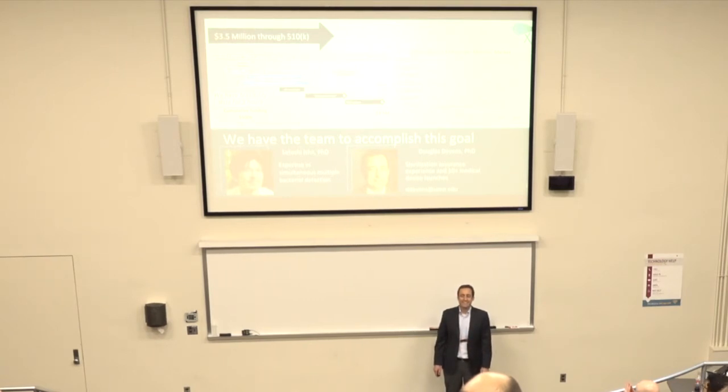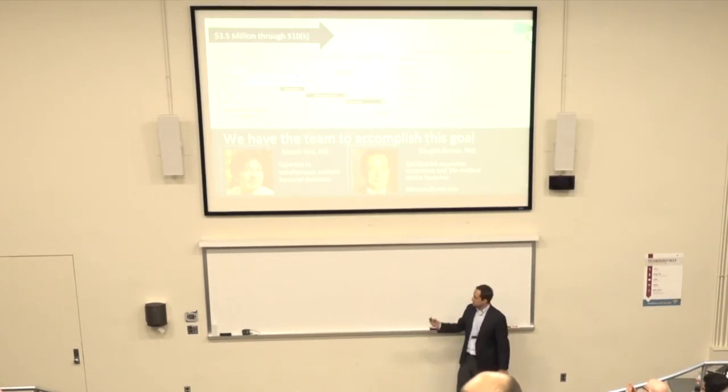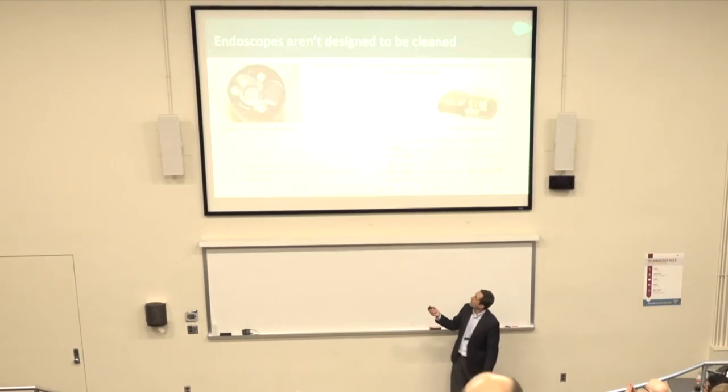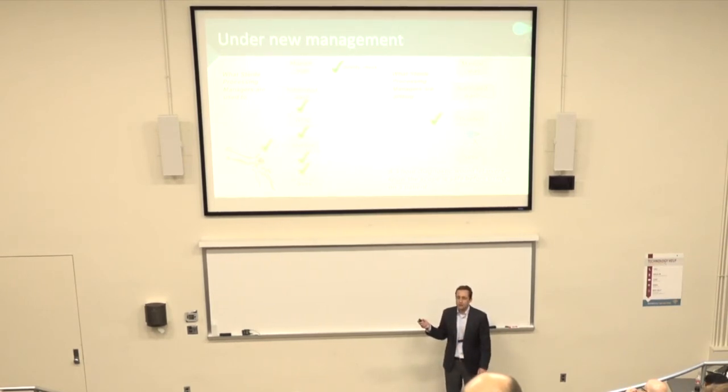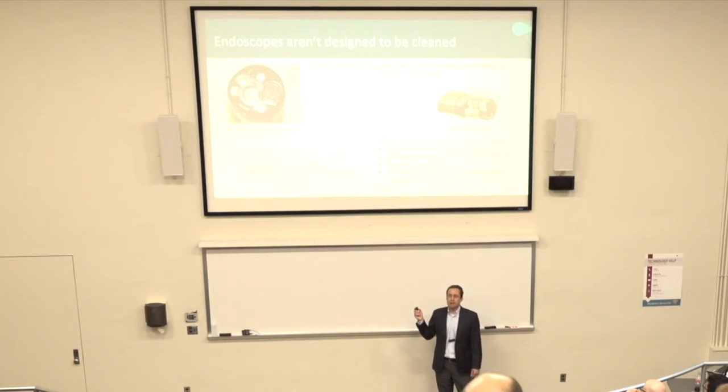What's the rate of failure today, when you did your market research? How do hospitals know today? Or how are they testing today? Well, today, they're not doing anything. And that's because the only test they got is a bacterial culture that takes 48 hours and requires a microbiology degree. What's the rate of failure? Based on the FDA MAUDE database, we calculate on the order of one in 10,000. But the problem is, each time that happens, you're getting 30 to 50 people infected. UCLA was 170. Virginia Mason was a couple hundred.